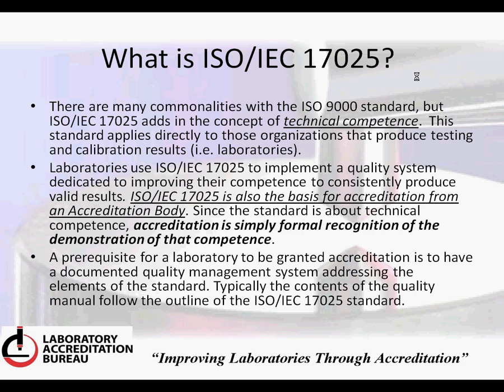There are many commonalities with ISO 9000, but ISO 17025 does add the concept of technical competence. This standard applies directly to those organizations that produce testing and calibration results — therefore, laboratories. Laboratories use the standard to implement a quality system dedicated to improving competence and to consistently produce valid results.